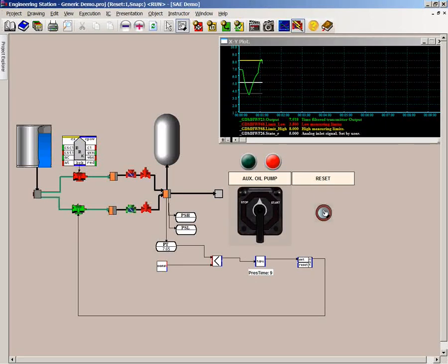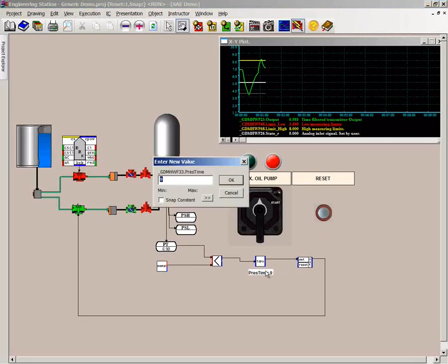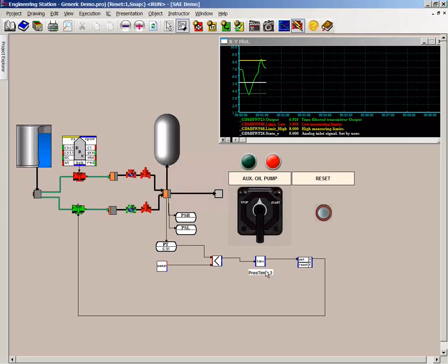the auto-start logic. Next, we'll change the design by shortening the time delay of the auto-start of the standby pump from 9 seconds to 3 seconds. Now, we can repeat the first exercise and observe the result. Indeed, this time we'll see that we did not reach the trip set point. With Master's integrated tools and plant design capability, we can do so much more.